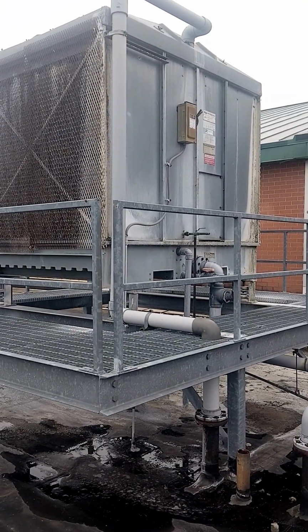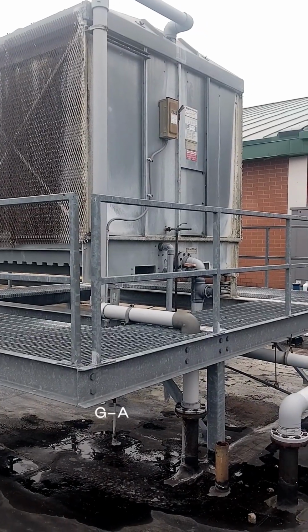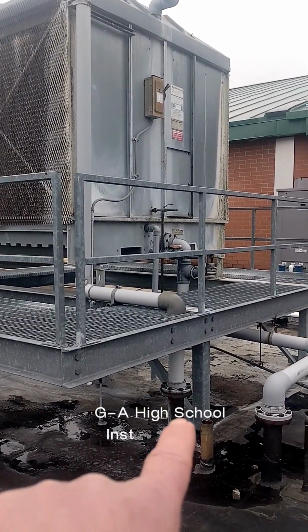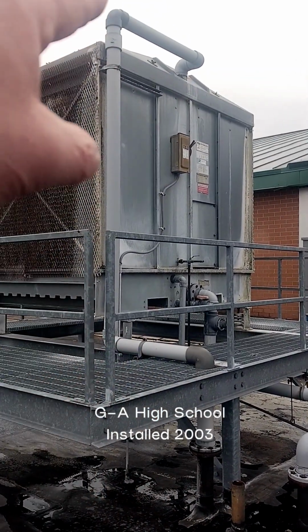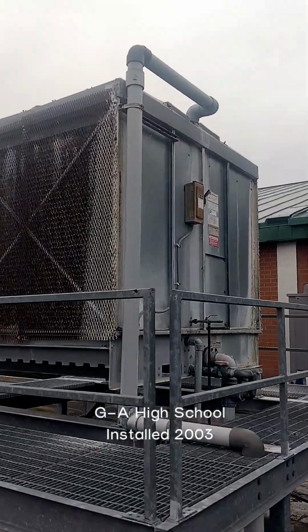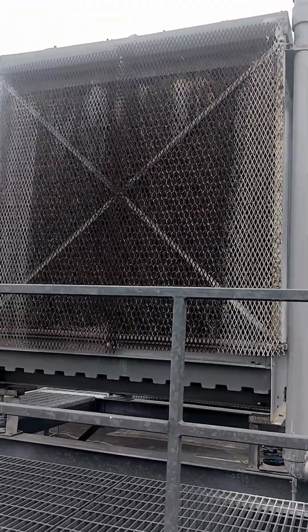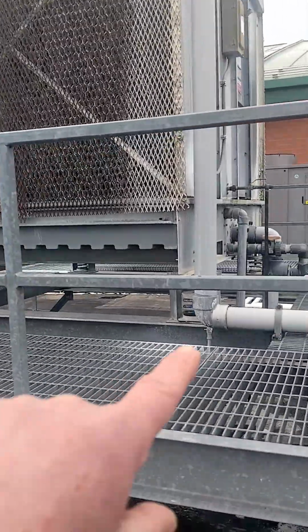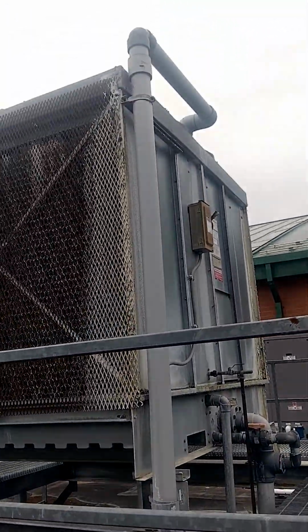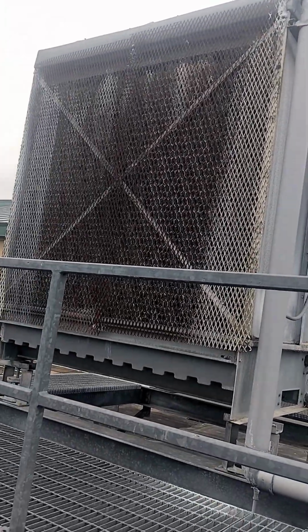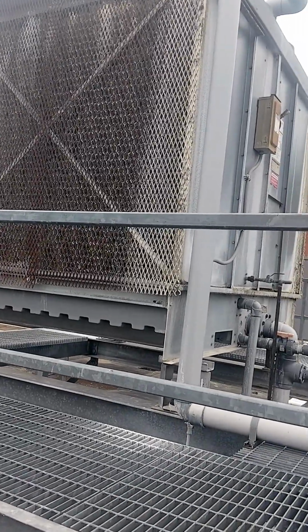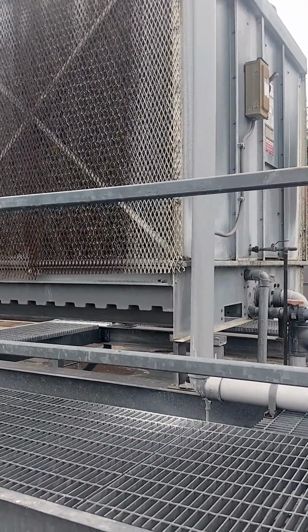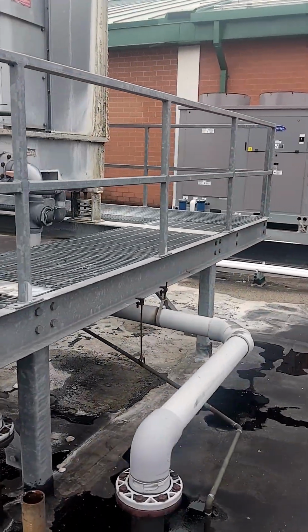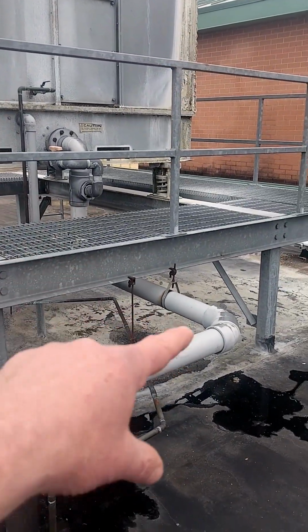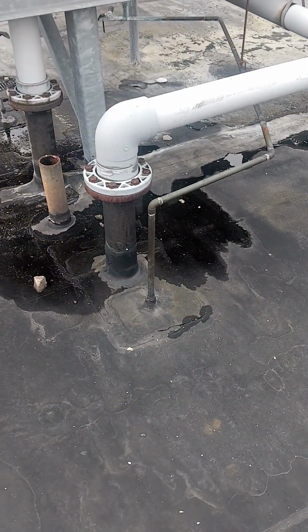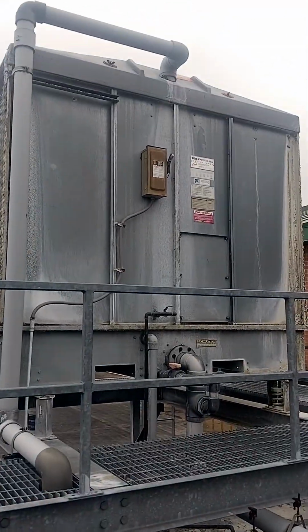This is the high school cooling tower. So the hot water is generated by the chillers, comes up this pipe over here and across into the top tank, and it rains down across this fill material here and settles in the bottom tank. There's a big fan on top that draws air in through this side and the opposite side that cools the water as it runs through the material. The water then runs from the bottom through this pipe and on down back to the chillers. And it repeats over and over.